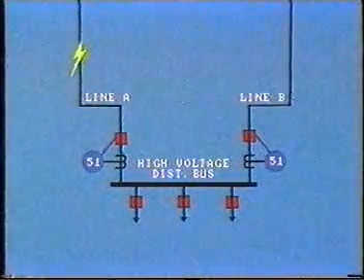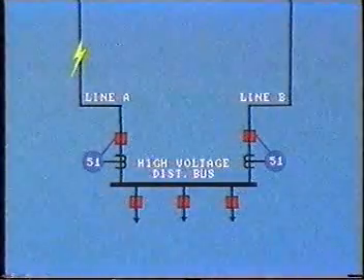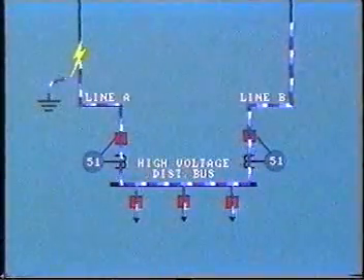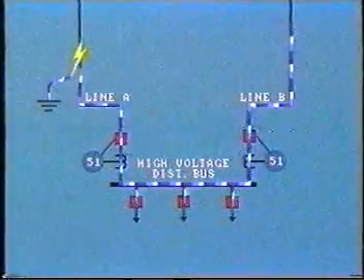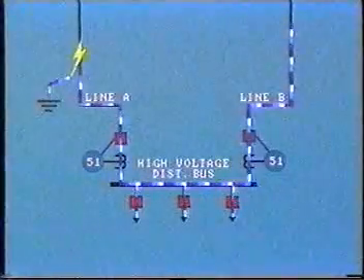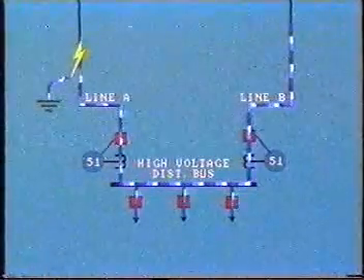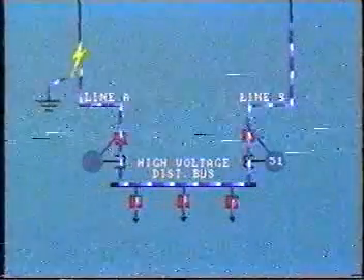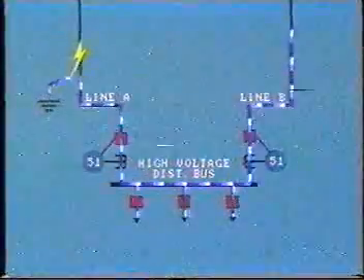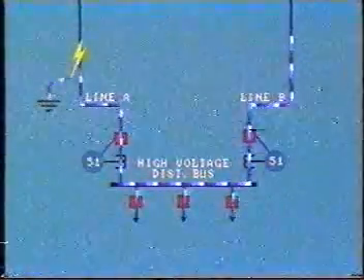Suppose a fault occurs on line A. Fault current will flow from line B through the bus to feed the fault on line A, in addition to the load on the bus. The overcurrent relay on line A will sense the overcurrent situation and begin to operate according to its inverse time characteristic.